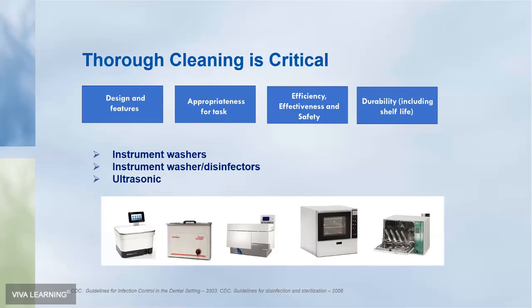So if you're using cassettes, you would place them in a rack. We were talking about aerosolization. It's important before starting the ultrasonic cleaner that the lid be closed, and that prevents aerosolization of bacteria. It's also important to leave that lid on until the ultrasonic cleaner has stopped. There are also cleaning efficacy tests available now for instrument washers, instrument washer disinfectors, and ultrasonic cleaners.